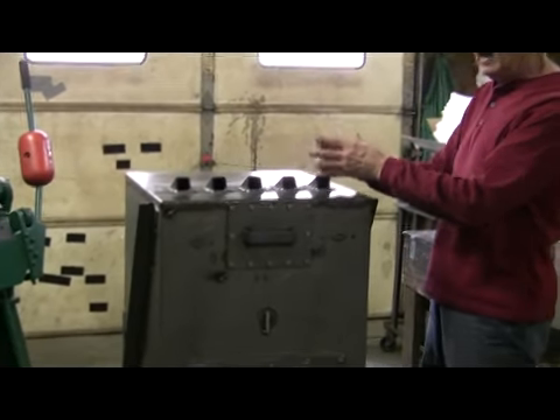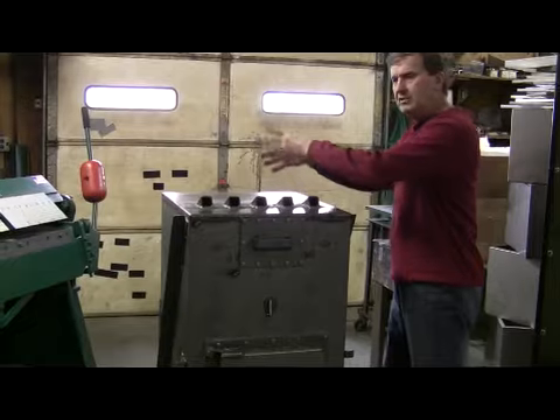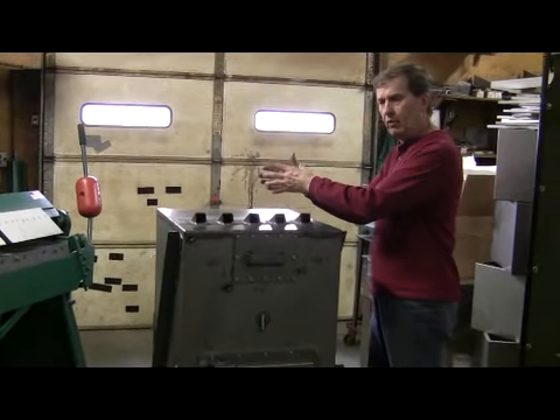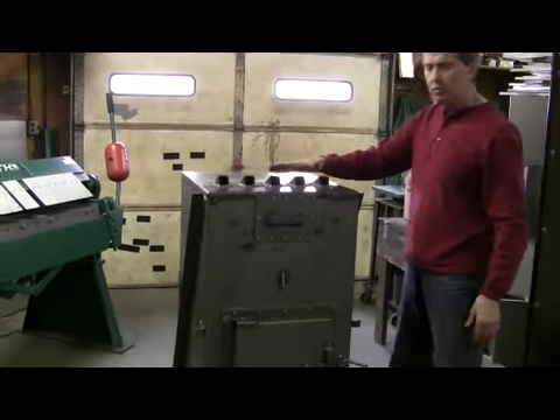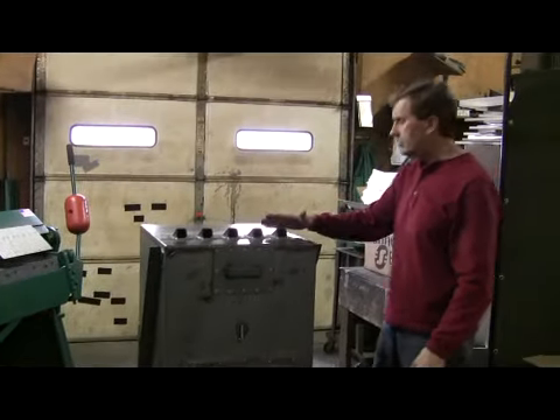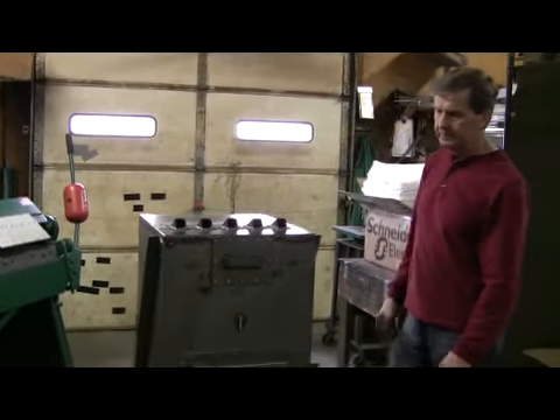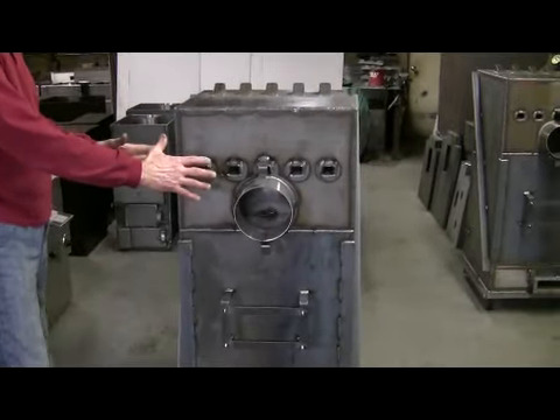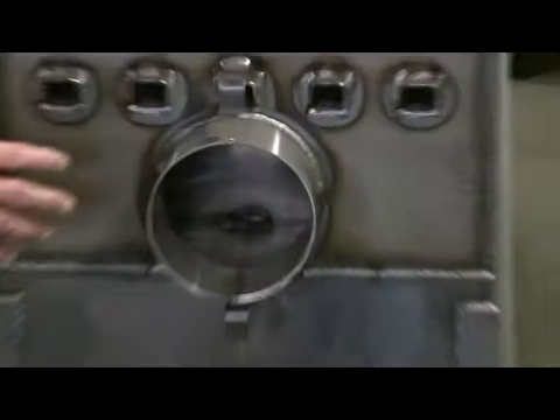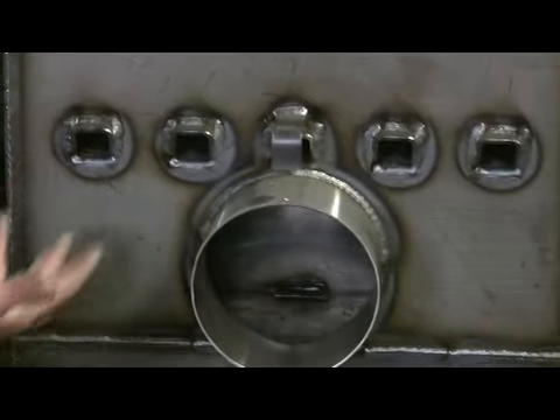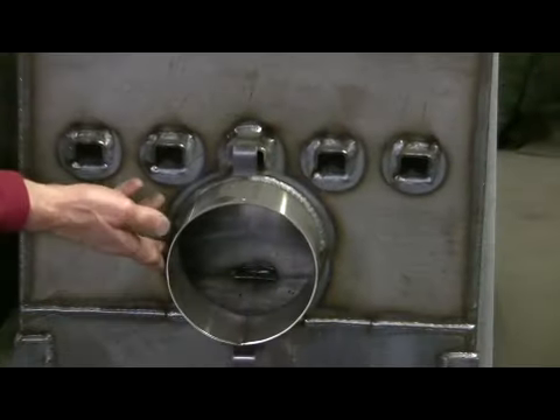Rather than having a furnace that puts 500-600 degrees up the chimney and wastes a lot of heat, this is only between 200 and 300 degrees that's actually going up your flue. Now this is the back view of that same Vapor Fire 200 furnace without the air jacket on there. You can see all those tubes have gone through the heat exchanger at an angle. You can see the stainless steel smoke collar here.